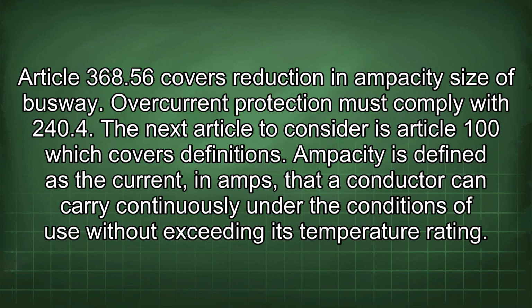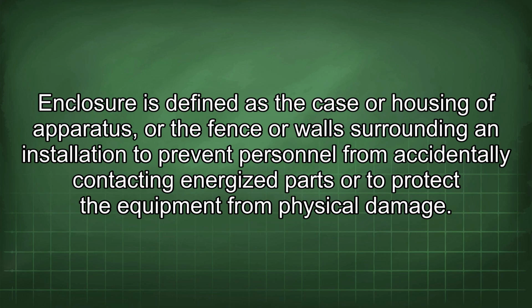Article 368.56 covers reduction in ampacity size of busway. Overcurrent protection must comply with 240.4. The next article to consider is Article 100, which covers definitions. Ampacity is defined as the current in amps that a conductor can carry continuously under the conditions of use without exceeding its temperature rating. Enclosure is defined as the case or housing of apparatus, or the fence or wall surrounding an installation to prevent personnel from accidentally contacting energized parts or to protect the equipment from physical damage.